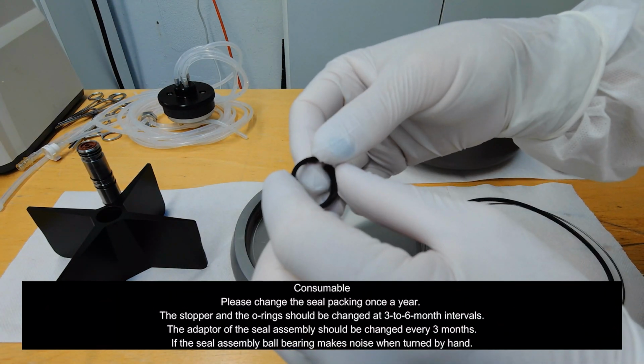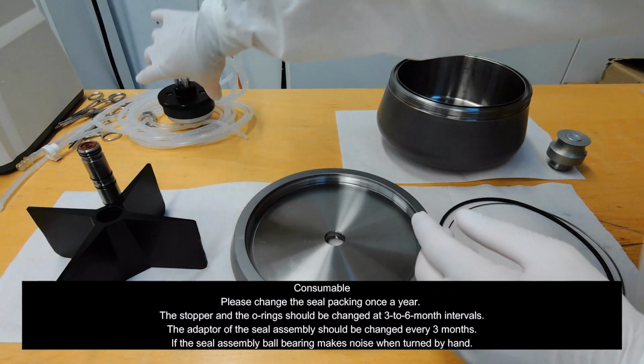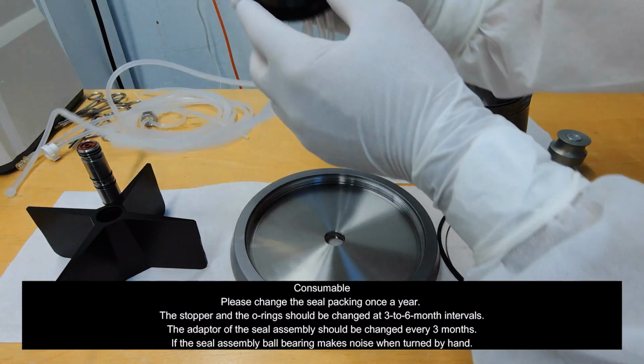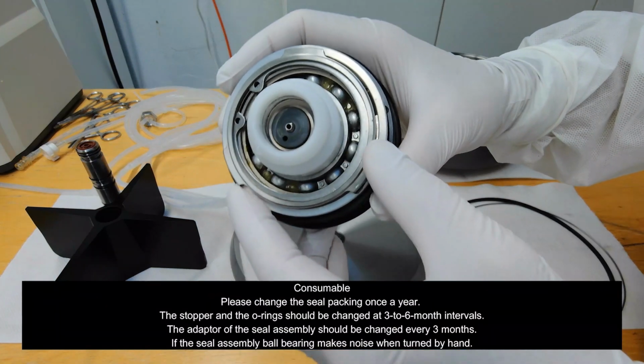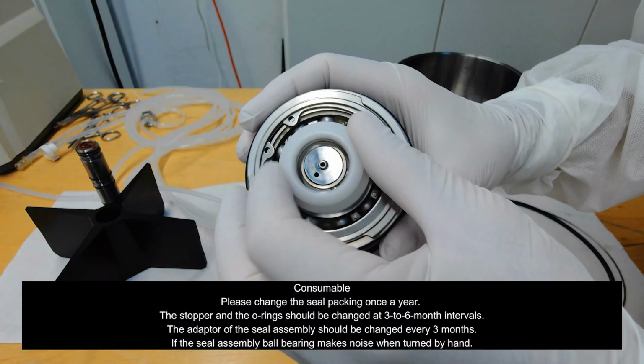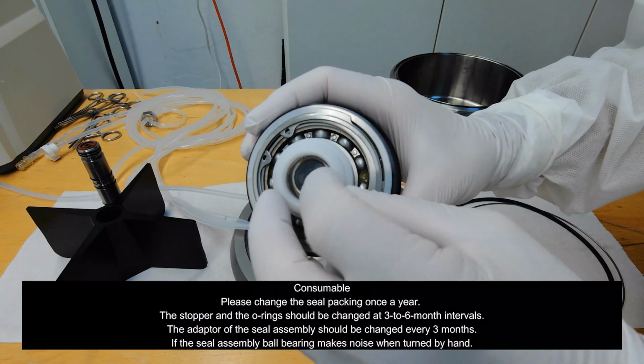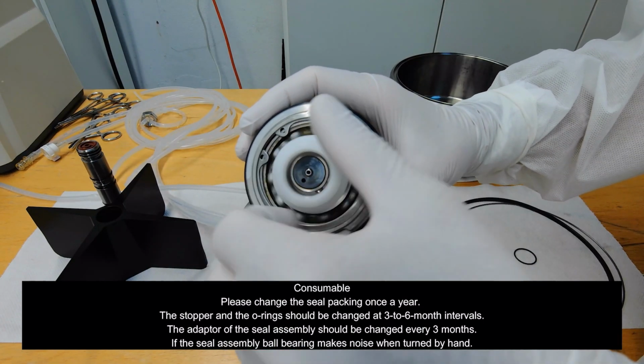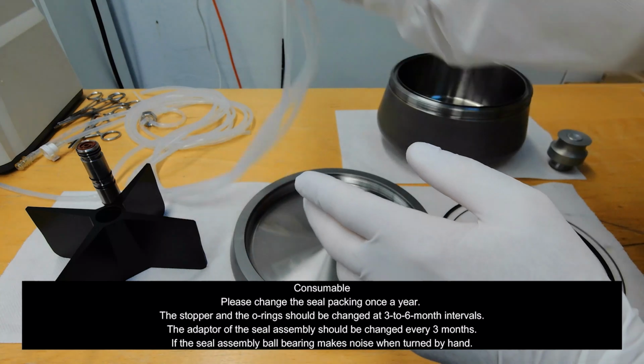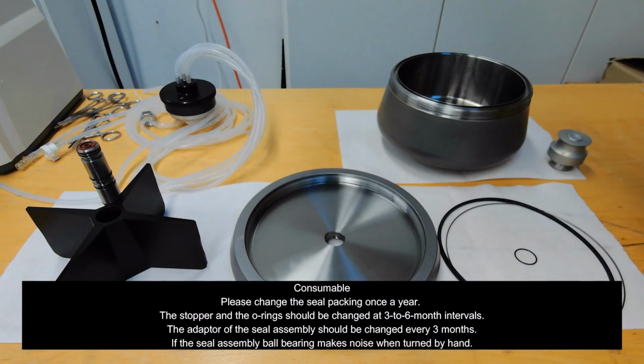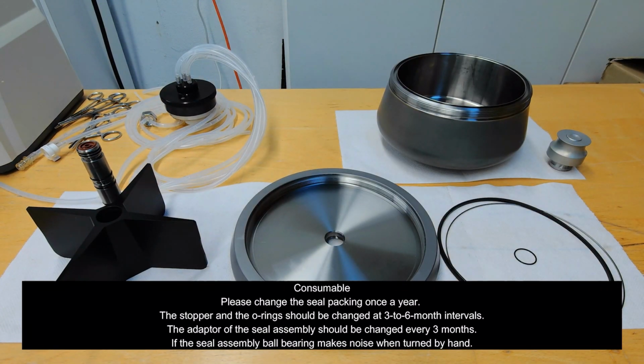Consumable. Please change the seal packing once a year. The stopper and the O-rings should be changed at 3 to 6 month intervals. The adapter of the seal assembly should be changed every 3 months. Change the seal assembly ball bearing if it makes noise when turned by hand.